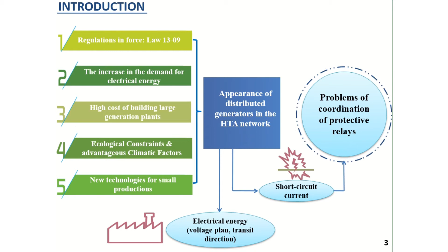The problem of coordination of directional overcurrent relays is considered as an optimization problem. Its objective function is the minimization of the sum of the operating time of all primary and backup relays in all fault locations studied, taking into account the constraints of selectivity, sensitivity, reliability, and characteristic of relays. The most important constraint is the coordination constraint. Coordination time interval (CTI) must be imposed between a primary and backup relay pair to maintain coordination. The value of CTI varies between 0.2 and 0.5 seconds, usually taken as 0.3 seconds.